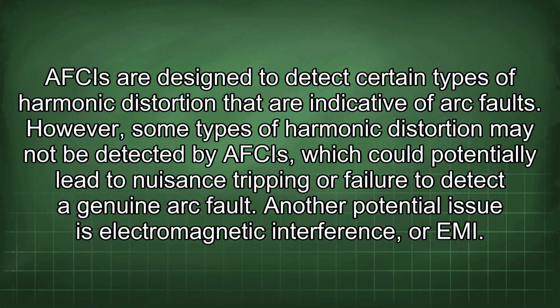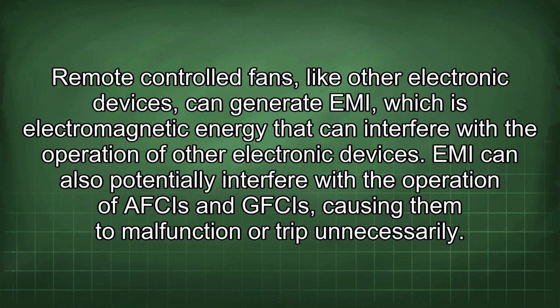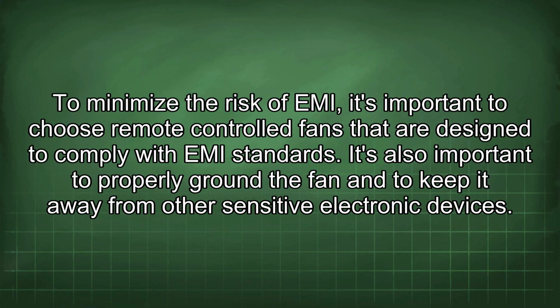Another potential issue is electromagnetic interference, or EMI. Remote-controlled fans, like other electronic devices, can generate EMI, which is electromagnetic energy that can interfere with the operation of other electronic devices. EMI can also potentially interfere with the operation of AFCIs and GFCIs, causing them to malfunction or trip unnecessarily. To minimize the risk of EMI, it's important to choose remote control fans that are designed to comply with EMI standards. It's also important to properly ground the fan and to keep it away from other sensitive electronic devices.